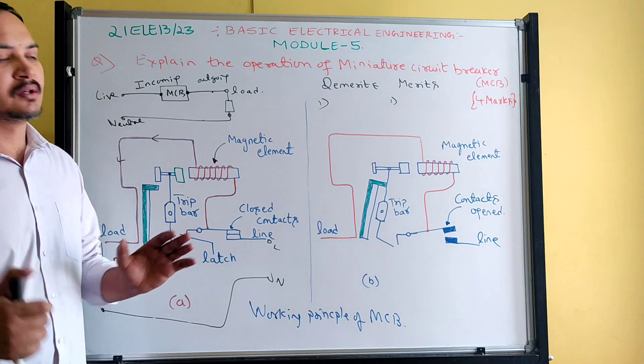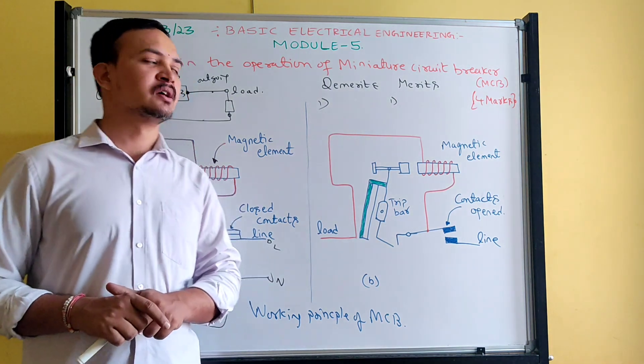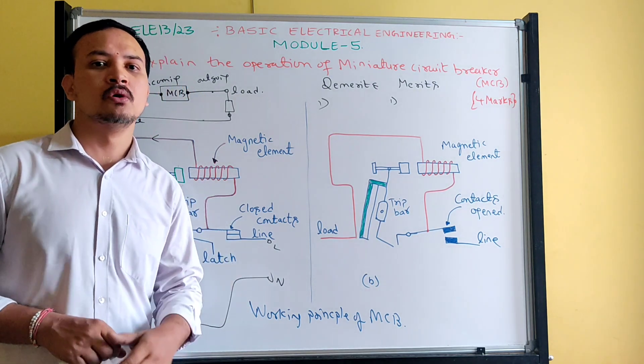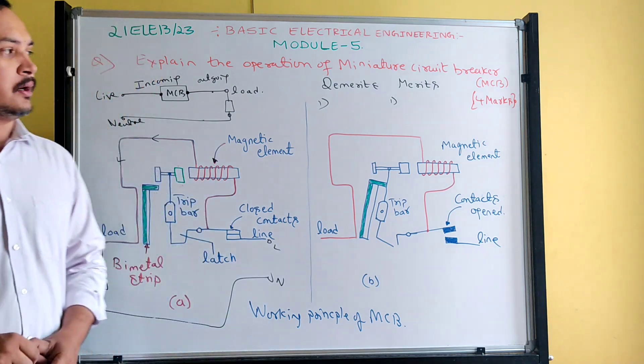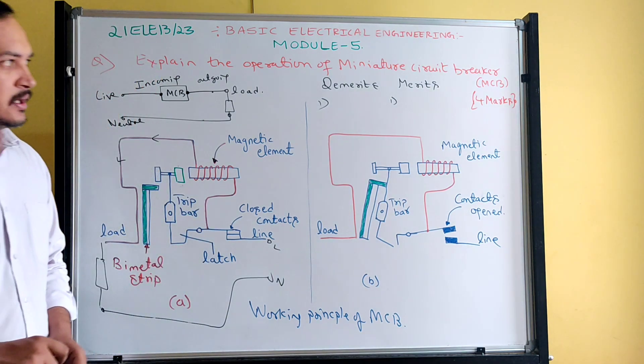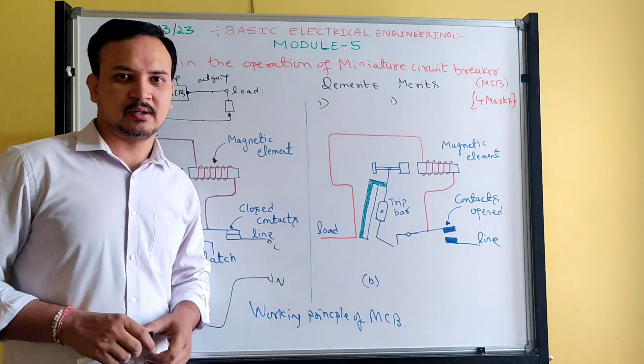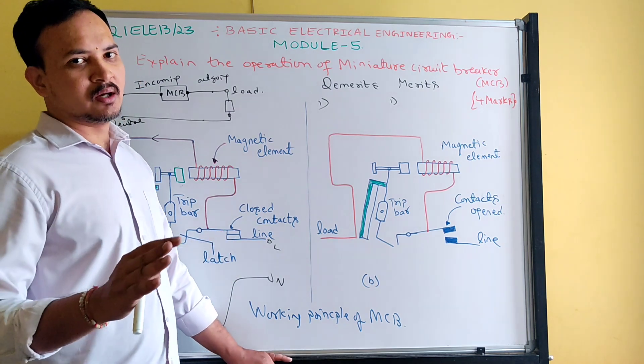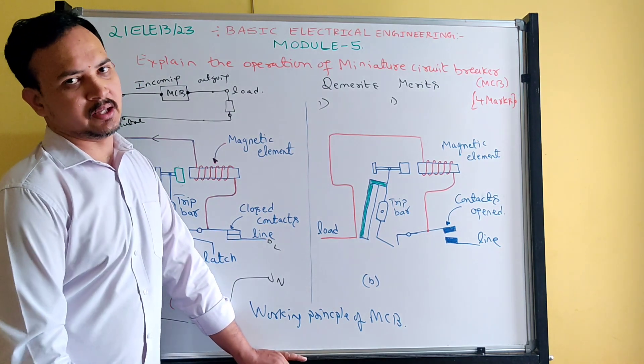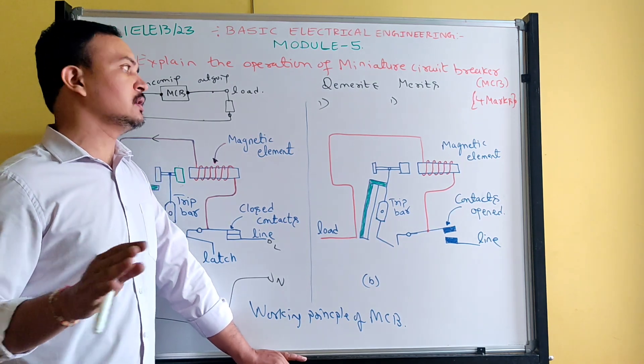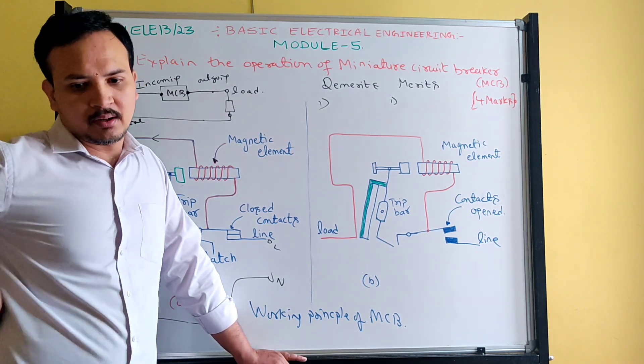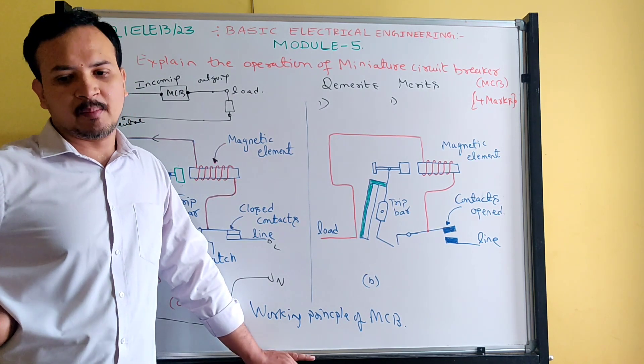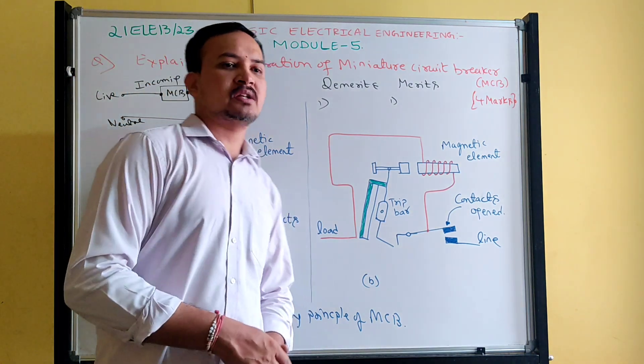Another demerit on the customer side is that MCB cost is higher than fuse. MCB is costlier compared to fuse. One more demerit is it cannot protect against earth faults. MCB cannot protect earth faults. Under such condition it is not protecting — only overloading and short circuit protection is what MCB is recommended for. MCB can be used in residential, commercial buildings, and also in industry.